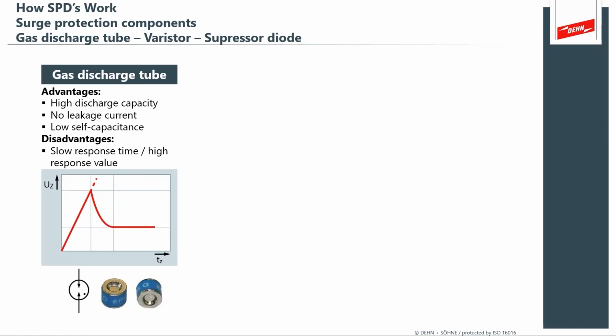So how do SPDs work? We have devices that you recognize as gas discharge tubes or spark gaps, or what we like to consider voltage switching devices. And what that means is, as the voltage rises, it reaches a peak and then switches on. And this is usually seen as a dielectric breakdown. For instance, in what might be considered a spark gap device, the gas inside of this small element will ionize and then spark. And you'll see this actually when you test these types of devices, you see them actually glow as the currents and the voltage produces enough breakdown to cause a small dielectric breakdown within the device.